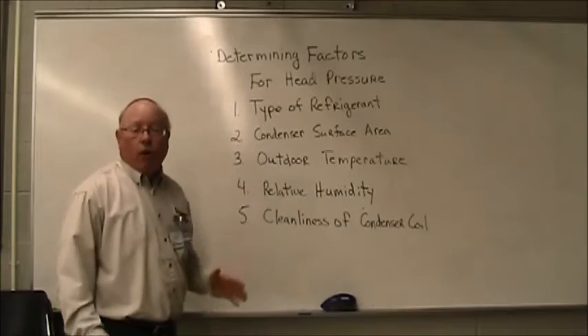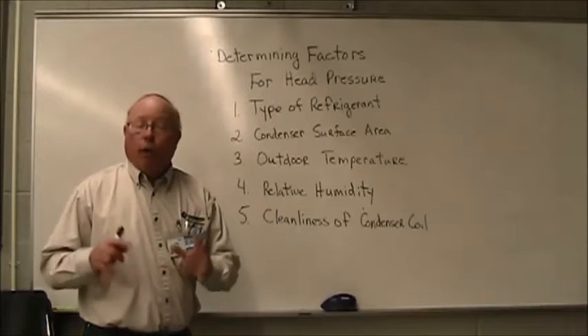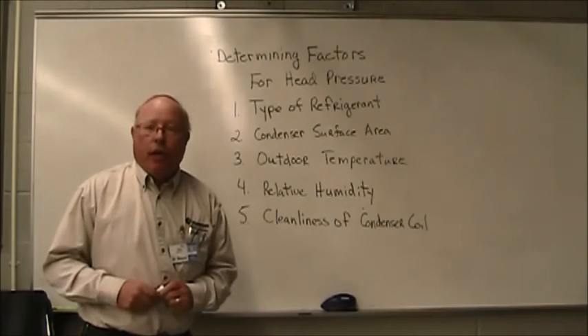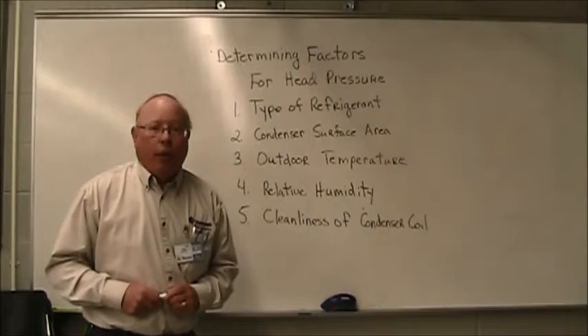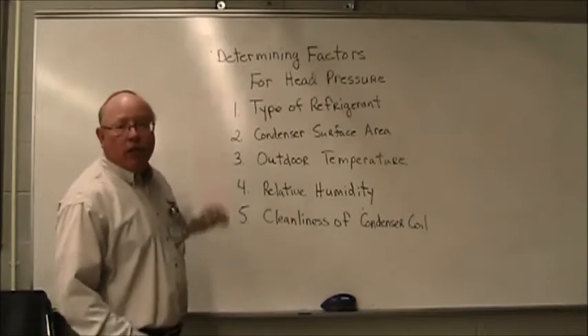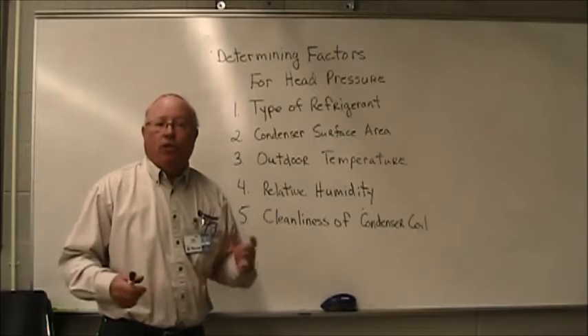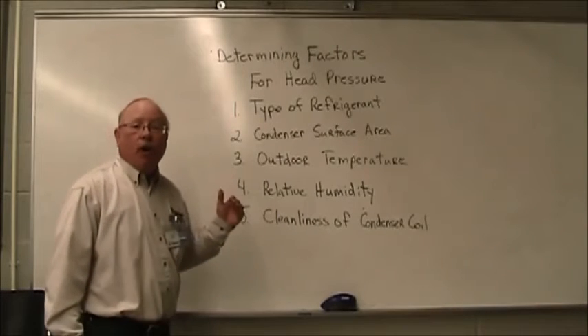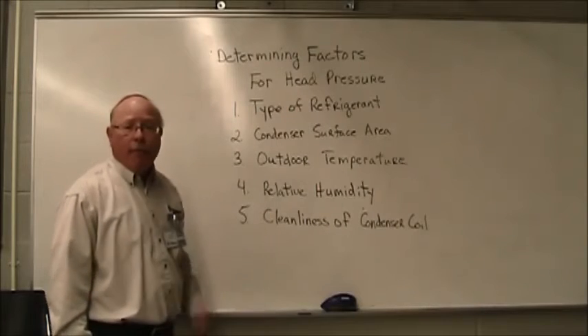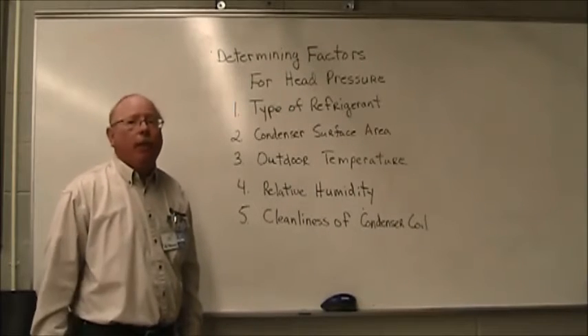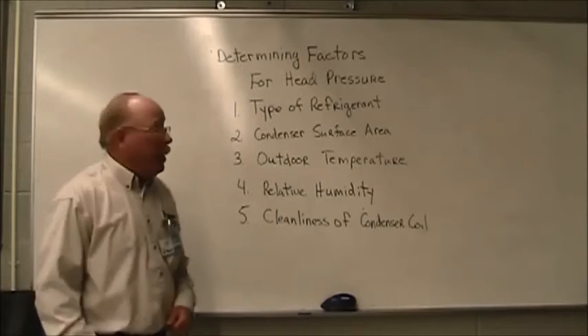All of these factors are going to determine what the head pressure is going to be on any given piece of refrigeration equipment. Not all refrigerants are the same — they have different boiling points, saturation points, and so forth. That means they're going to have different pressures at different temperatures. So the type of refrigerant is definitely going to be the number one determining factor as to what your head pressure should be.